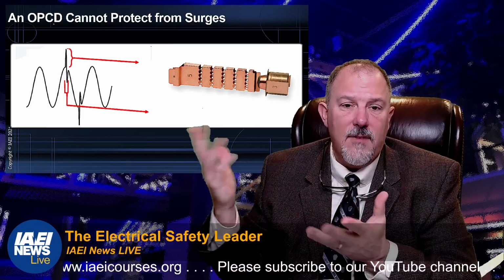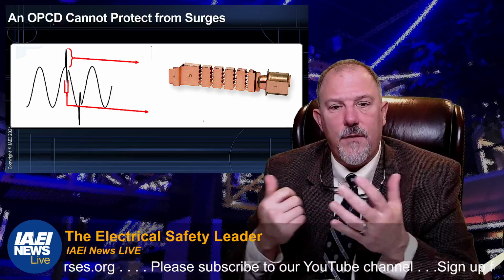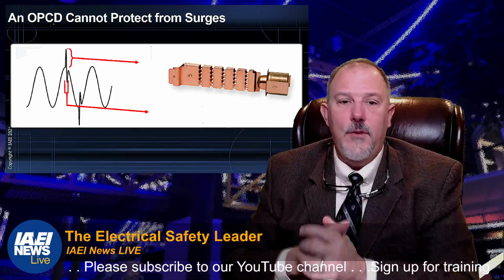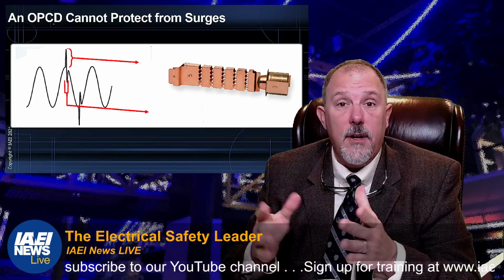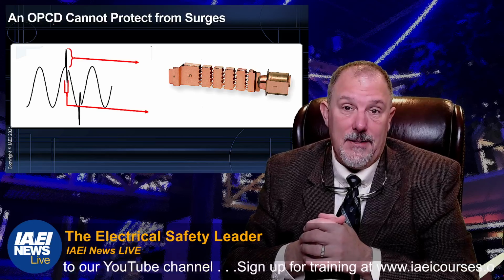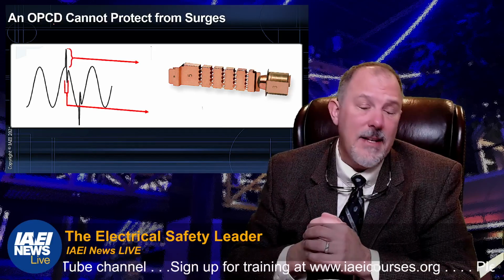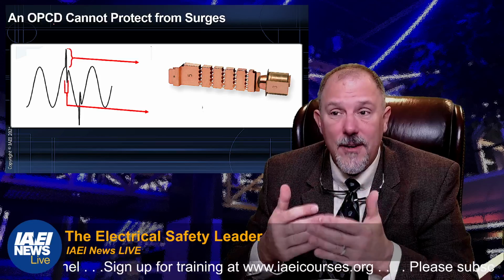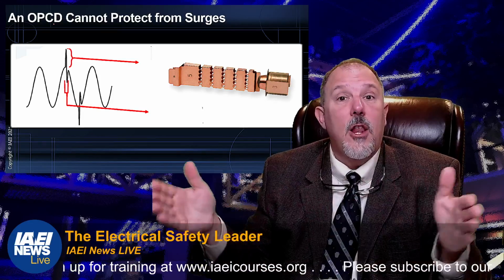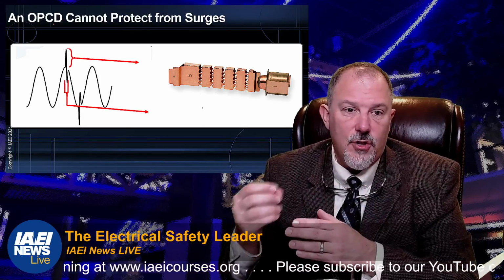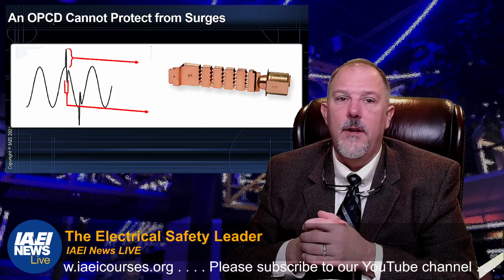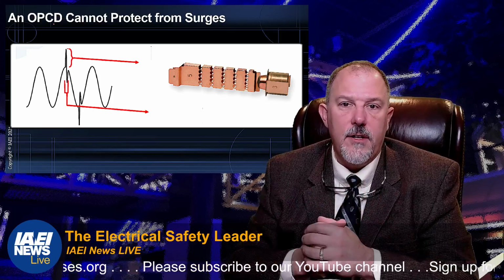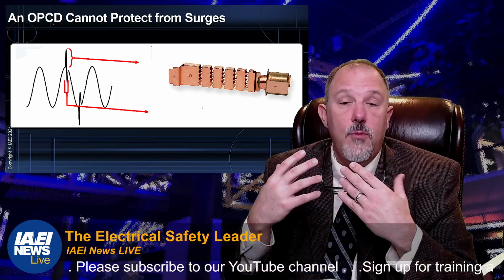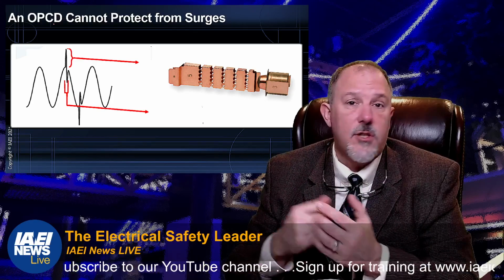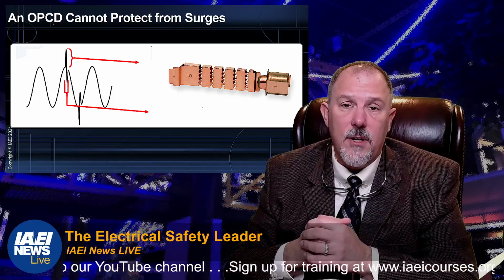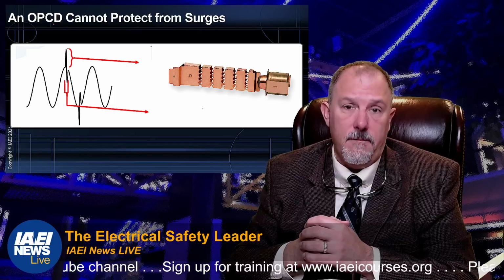And an overcurrent protective device. This is the inside of a fuse. That's your fuse element. Do you know what opens a fuse? Current. And lots of it. Do you know what trips a breaker? A thermomagnetic circuit breaker especially. Current. And lots of it in a long duration. These transient voltage events do not produce enough current that lasts a long enough time to open an overcurrent protective device. So a circuit breaker or a fuse is not going to provide you with that protection.